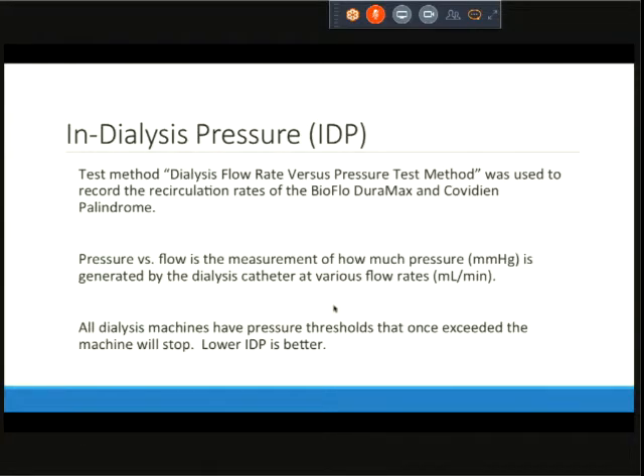The next thing we looked at was in-dialysis pressure. The test method was to use the dialysis flow rate versus a pressure test method, and it's looking at, again, recirculation rate as well as the actual in-dialysis pressure. The pressure versus flow is the measurement of how much pressure is generated by the dialysis catheter at the various flow rates. Again, we looked at 200, 300, and 400. And all dialysis machines have a pressure threshold that once it's exceeded, the machine will stop. Therefore, lower in-dialysis pressure is better.